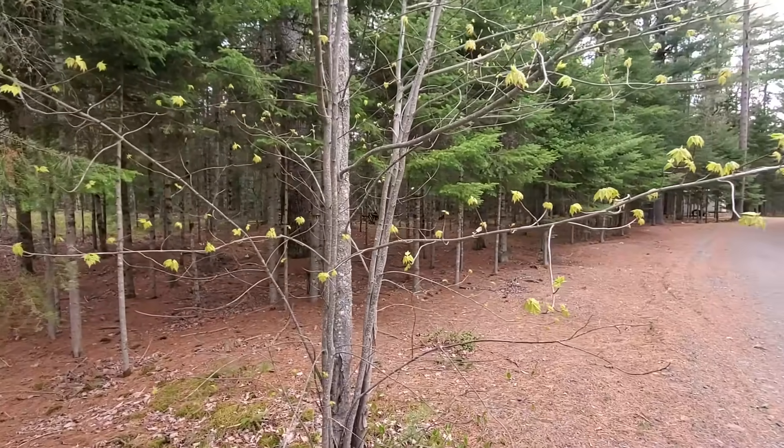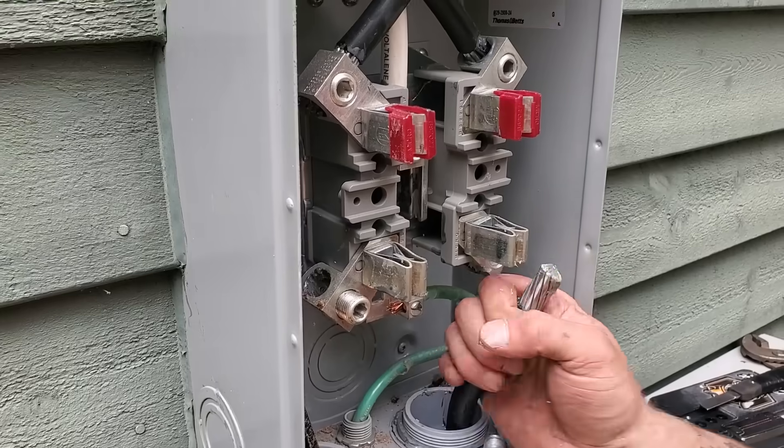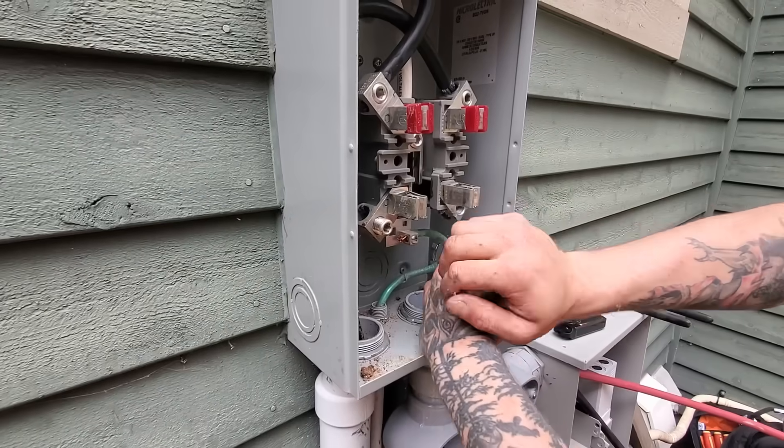Hey, what's up guys? You're watching Bob's Decline. Today we're meeting an electrician at a neighborhood where pretty well all the wires are buried underground. It's probably my favorite neighborhood in the whole city — completely surrounded by huge pine and spruce trees and the power lines are all somewhere in there. It looks nice, but makes things pretty hard to work on. The guy's got to get inside the meter socket, so we can't have that meter socket energized while they're working in there. We're going to isolate those lines. It's a little different than just cutting the two hots on the roof — we can't actually see where those wires are going, so there are a few extra steps to take in order for the electrician to perform their work safely.